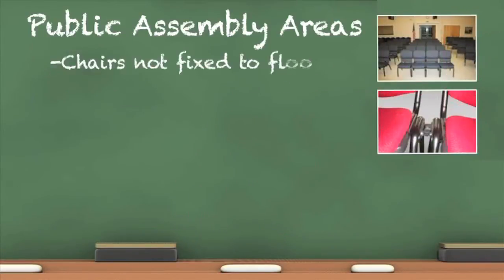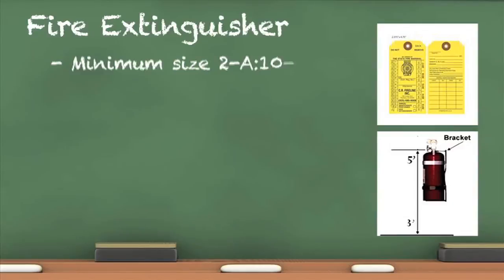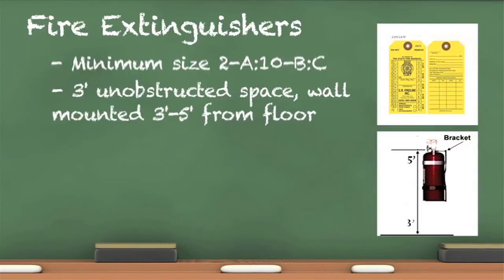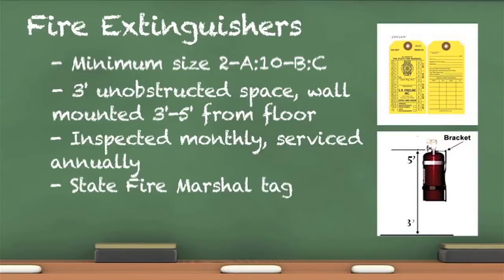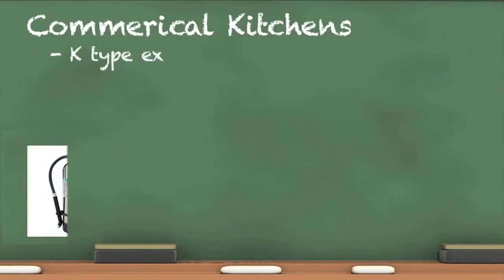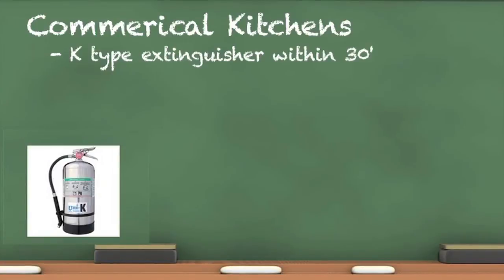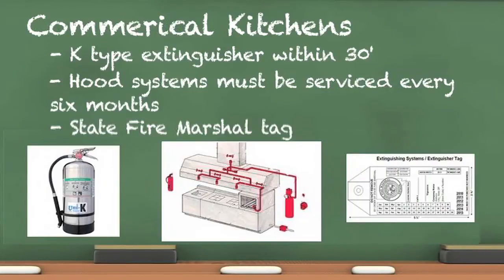Chairs set up in a theater-style arrangement and not fixed to the floor shall be bonded in groups of three or more when the occupant load is 200 or more, unless tables are provided. The minimum size for fire extinguishers is 2A10BC, and a minimum of 3 feet of unobstructed space is required for access. All fire extinguishers must be visually inspected monthly and serviced annually; records of this inspection and service shall be kept on site. In all A occupancies with commercial kitchens, K-class extinguishers are required and must be serviced annually. Hood extinguishing systems are required to be serviced every six months. State fire marshal tags are required for all extinguishing systems and extinguishers.